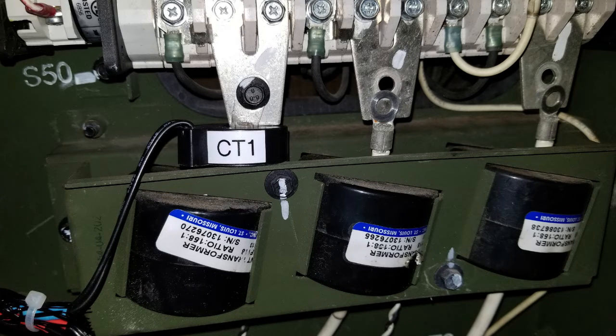The remaining sensors to be installed are 3 current sense transformers on the supplied wire harness. To install each one, simply remove the bolt securing the output leads from S50, the phase, voltage reconnection switch, and slide the wire down, insert the supplied current transformer, and then slide the lead up through the current transformer, and then resecure the leads back to S50. Repeat for the other 2 current transformers.